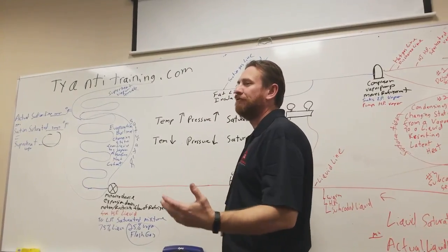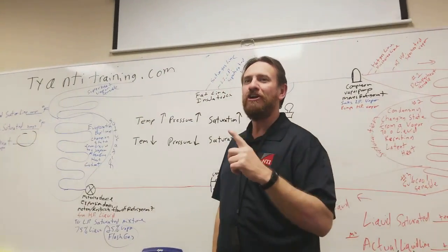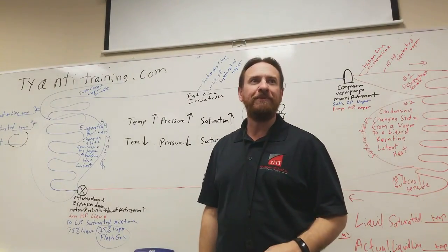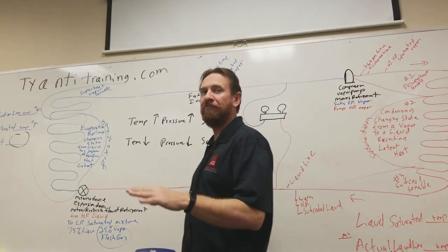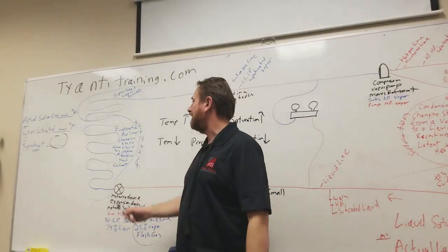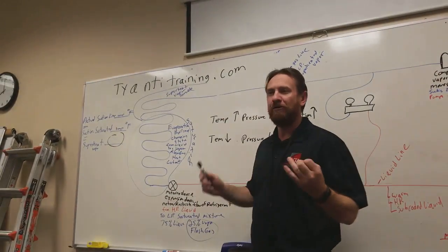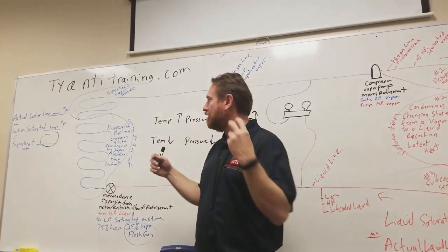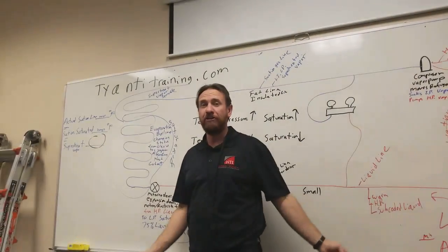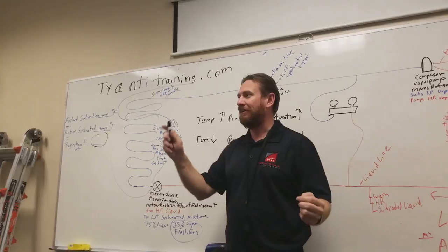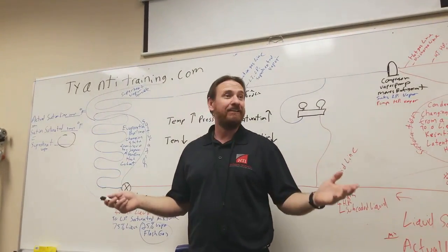So the reason the unit will freeze is because the saturated temperature drops below 32 degrees Fahrenheit. The number one cause, we're going to visit this later, is airflow. Dirty filter, bad fan, bad ductwork, blocked return, and so on. The number 2 cause is low refrigerant. What will cause it to be low in refrigerant? We'll come back to that. A leak. Find a leak.